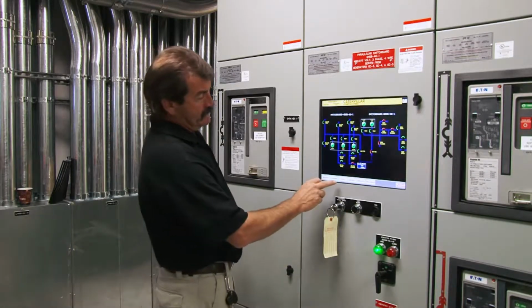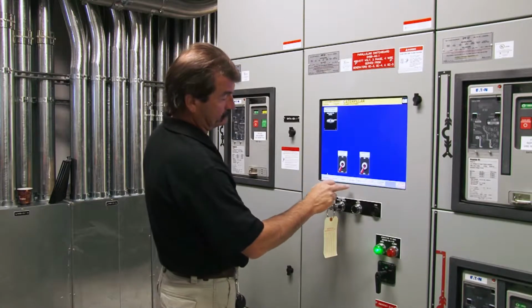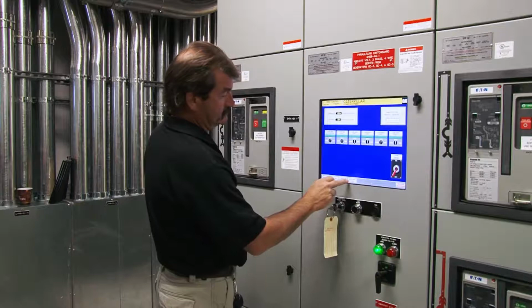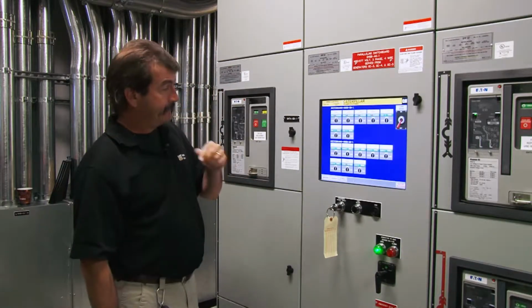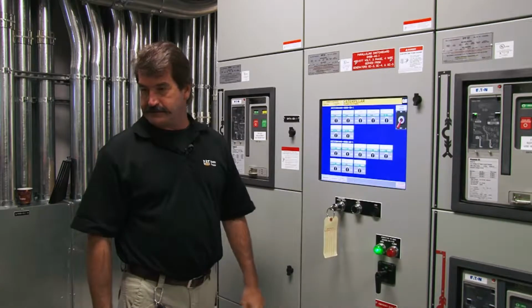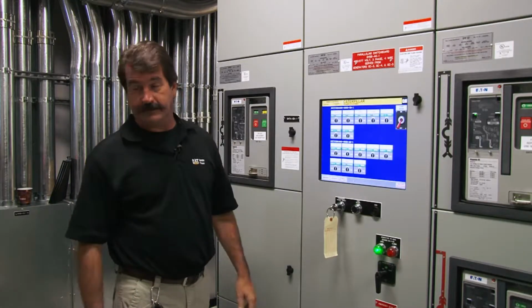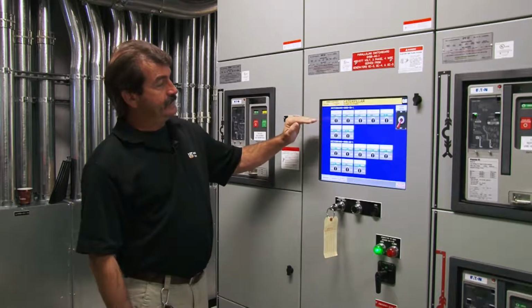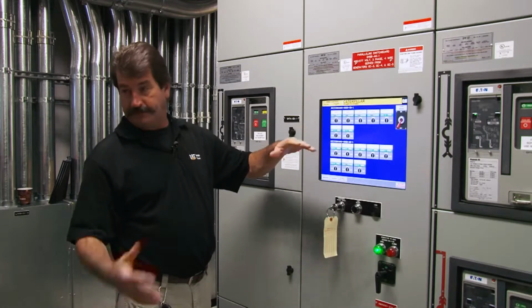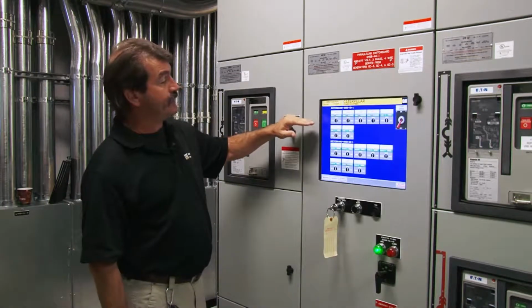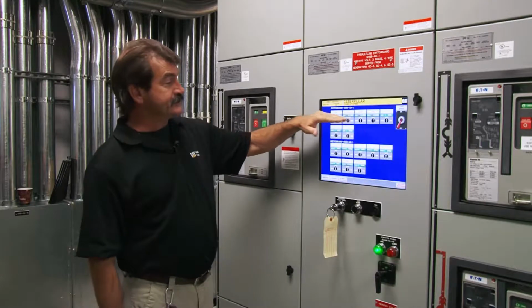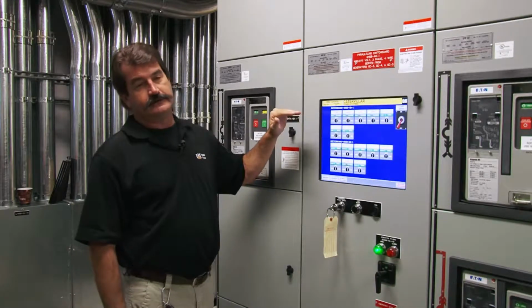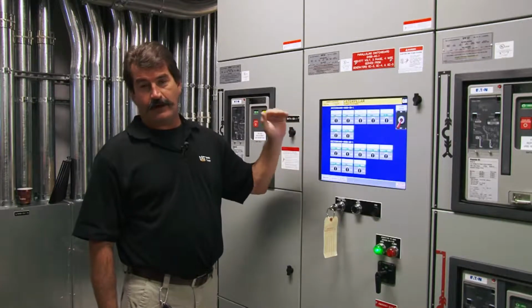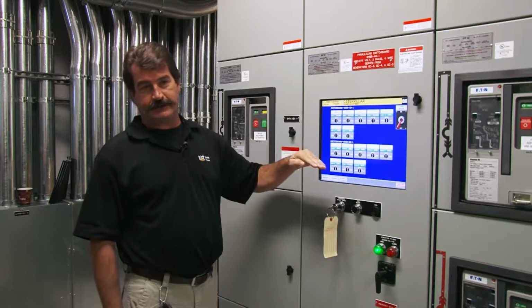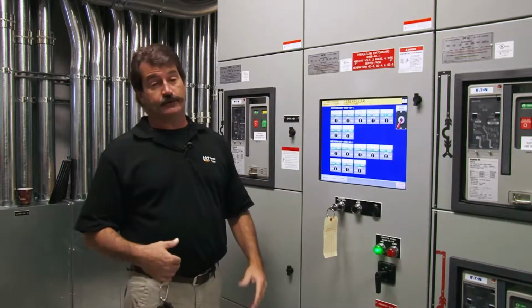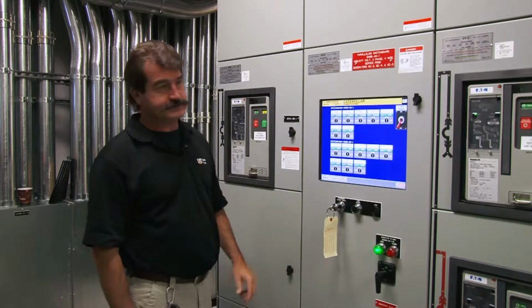Okay. So we can look at this right here, which will tell us how the circuit breakers are set up, like you're talking about. Their order that they're going to come in. And we'll go over this one more time. I'm sure y'all went over this with Pina, but we'll go over it one more time. So if it's ESS, that's essential. That is a normally closed circuit breaker, always closed, will never be shed, okay? It's absolutely essential or critical, however you want to call it. Those are the ones that you have closed in right now.